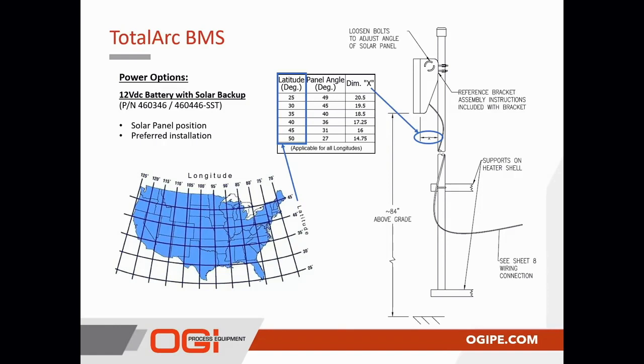We also want to make sure that panel is clean. Just by the fact that we've installed it facing the southern sky, we've got the right angle. But if it's got snow or any kind of debris on it that's blocking it, the actual performance of that solar panel will be degraded. A properly positioned, maintained solar panel will provide about 14 to 17 DC volts to the power converter.